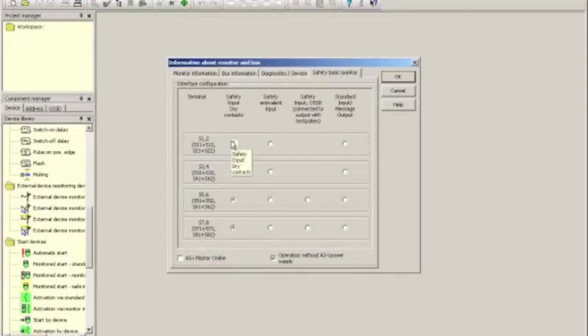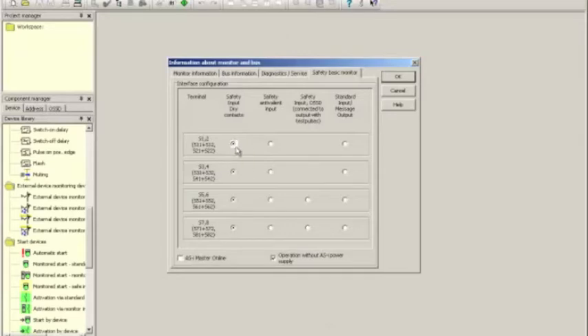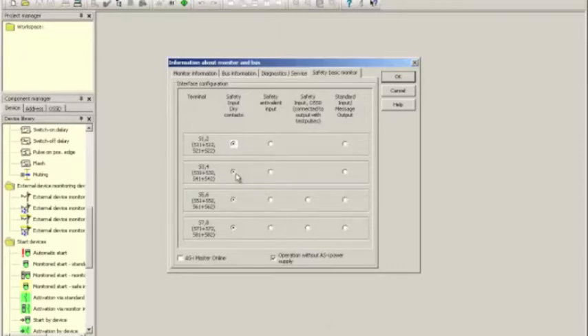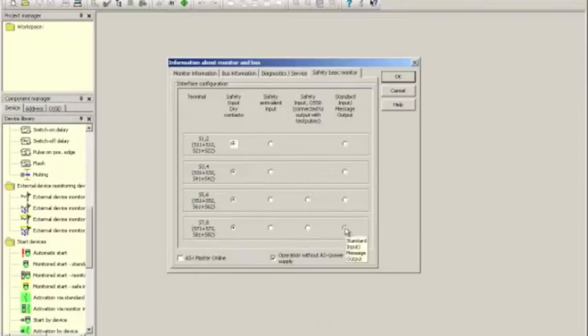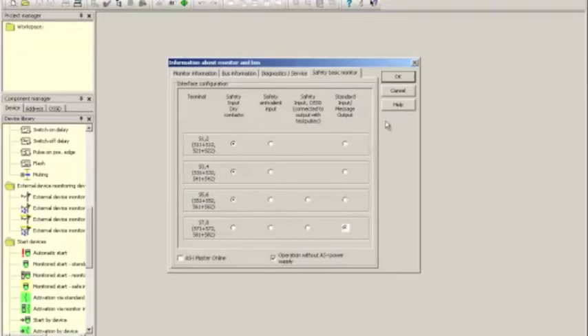Still as before, as for the example with the three e-stops, the sets S1, S2 are dry contact for the e-stops. S3, S4 will be dry contacts for the first magnetic door switch and S5, S6 is going to be utilized for the second magnetic door switch. There will be no safety device on S7, S8 and instead we will configure that input set again as a standard input-output so that we can have a reset for the e-stop. Actually, before we do that, as before, we want to disable this checkbox down here. Then click OK.